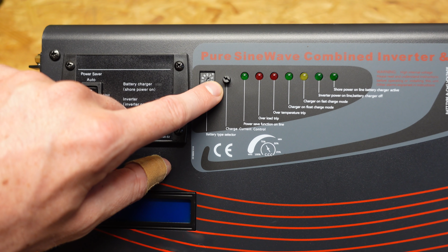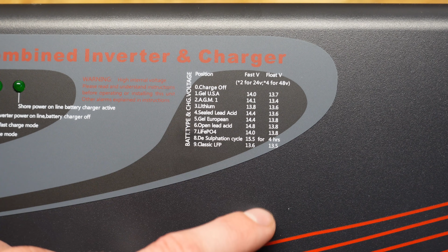Here we can see the different charge parameters, the float and fast charge voltages for various chemistry settings. This inverter is somewhat unique in that it has an LFP, or lithium iron phosphate, mode. In fact, there are three modes here: classic LFP, lithium iron phosphate, and a standard lithium mode.